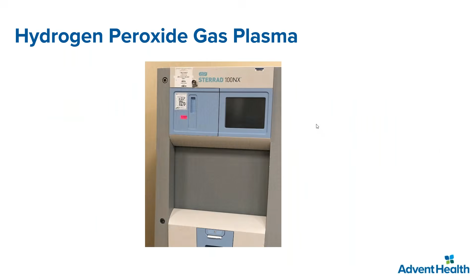The hydrogen peroxide gas plasma is safe for the environment and leaves no toxic residual. The cycle time can go from 25 to 75 minutes. It's used for heat and moisture sensitive items since the process temperature is below 50 degrees Celsius. It's very simple to operate. The only thing that you need is an electrical outlet, and it's compatible with most medical devices. In times of war, if they have an electrical outlet, they can use it, whereas the installation of a steam sterilizer is a whole process. It's going to stay there forever, it cannot be moved.